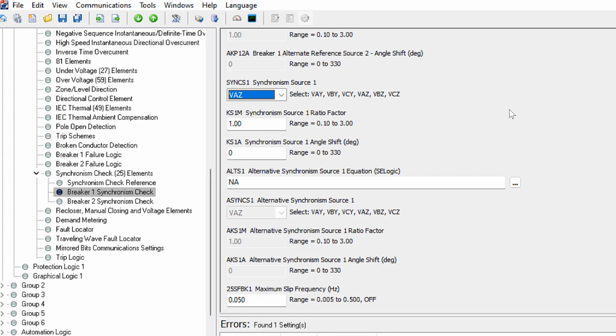You will need to change that if you were using a different signal for the breaker number 1. So if you were using the B phase, for example, as your connection for that side, you will need to set this to VBC. It just depends on where you wire the single phase input from the bus side in the relay. In this case, again, I said that the bus 1 side, we connected that to the VAZ input of the relay, and the bus 2 bus side voltage, we connected that to VBC. Since this element is for breaker number 1, we can set this to VAZ.